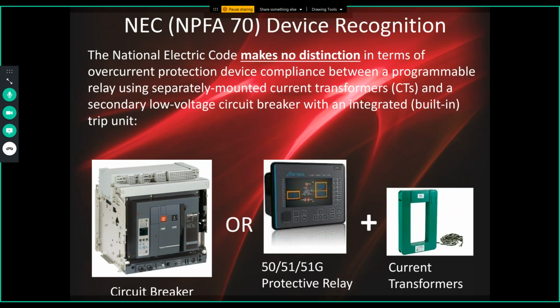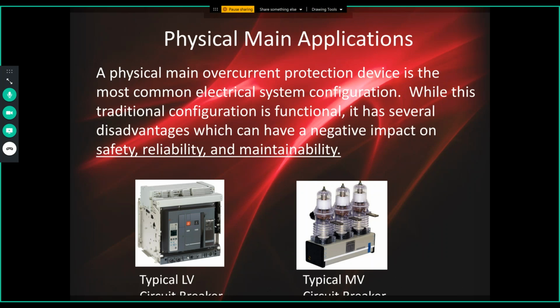So in terms of National Electric Code device recognition, again, there's no difference between that physical circuit breaker you see in the lower left-hand corner there and taking a protective relay, adding protective class, relay class, current transformers, and tripping a primary or asserting a primary overcurrent protection device. A physical overcurrent protection device, without doubt, is the most common type of electrical overcurrent protection in the United States. And while it's traditional and while it's functional, I would argue that it has several significant disadvantages in terms of safety, reliability, and maintainability.